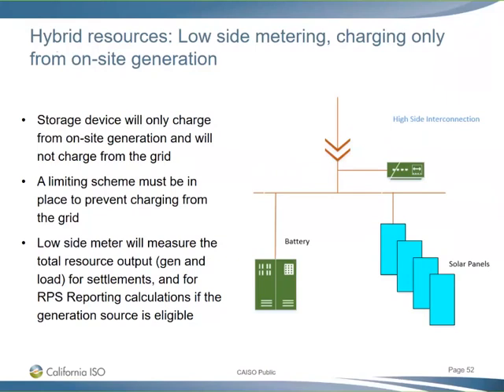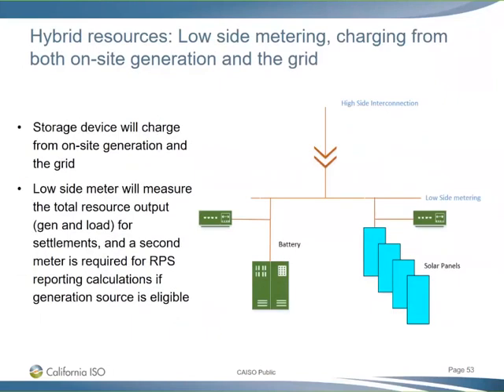The last one is low-side metering with the capability for charging from both on-site generation and the grid. Similar to the high-side case, you'll have 2 meters, but since the battery can charge from the grid or on-site generation, there's no requirement for a limiting scheme. You'll have 2 meters, one at the battery storage device and one at the solar panel, to calculate the RPS reporting requirement. This would also work for other resource combinations, like wind and storage.